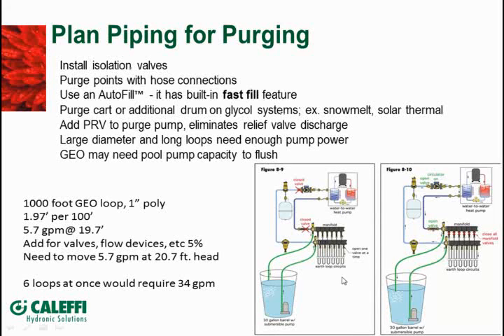You want to be able to break that down loop by loop to be able to purge it out. And this is in one of our hydronics issues. We just show you the procedure for that. Again, we're pumping out of the container that has the fluid that we're putting in there. We're pumping in the one manifold, we're going out through our loops here, and then we're burping it out here.